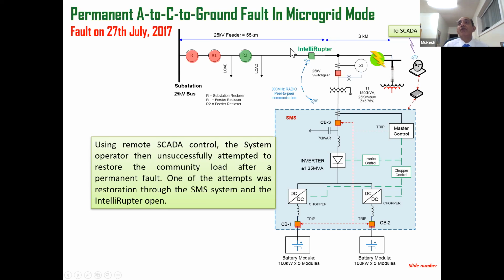But let's take it, there's a permanent fault here. This recloser will open and this interrupter will open and the fault is isolated. The recloser will reclose. If the power is restored, someone will close this and the power will go back. But if this is a permanent fault, the reclose attempt will fail.